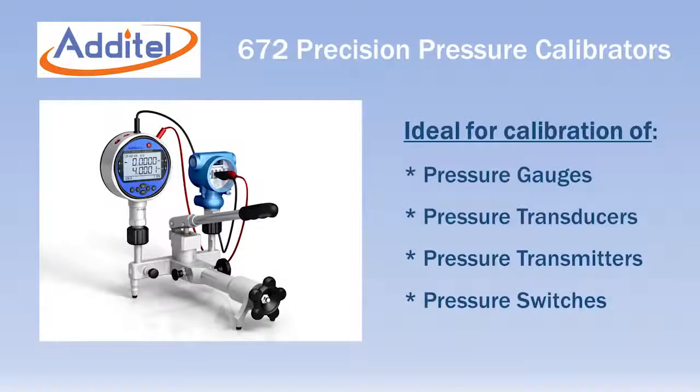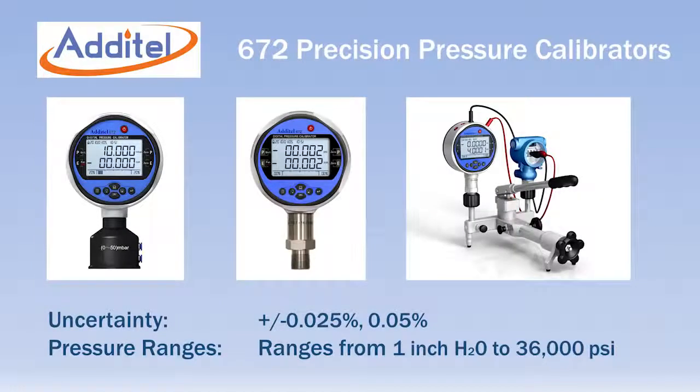The 672 is ideal for testing pressure transducers, transmitters, and switches. Like the 681 digital pressure gauges, the Additel calibrators are available in ranges from 1 inch of water to 36,000 psi and with uncertainty of either 0.025% or 0.05% of full scale.